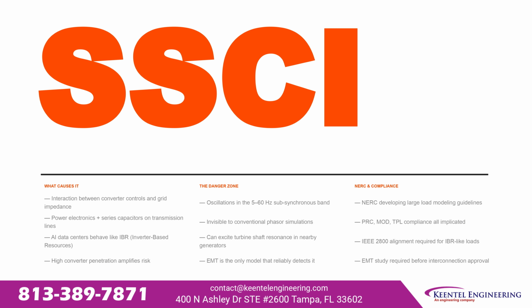On compliance, NERC is developing large load modeling guidelines. PRC, MOD, and TPL compliance are all implicated. IEEE 2800 alignment is required for IBR-like loads. An EMT study is required before interconnection approval.